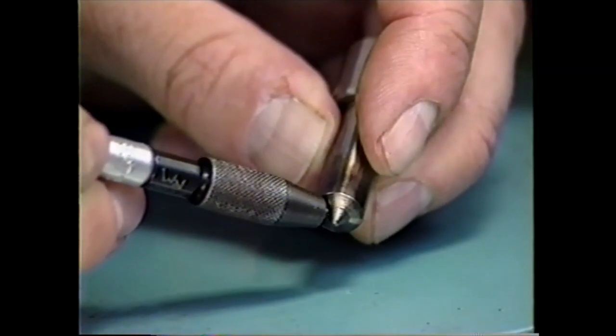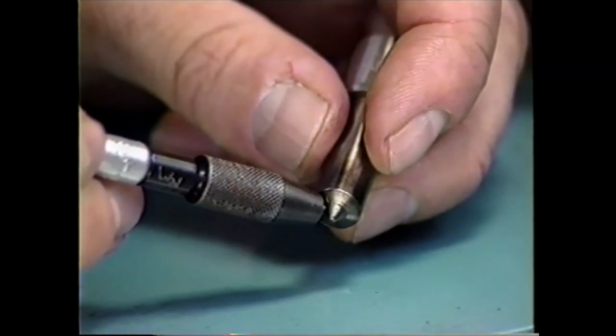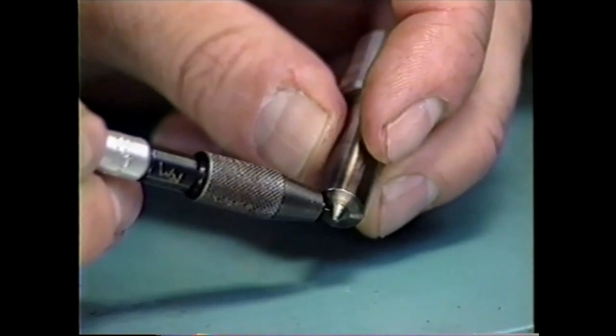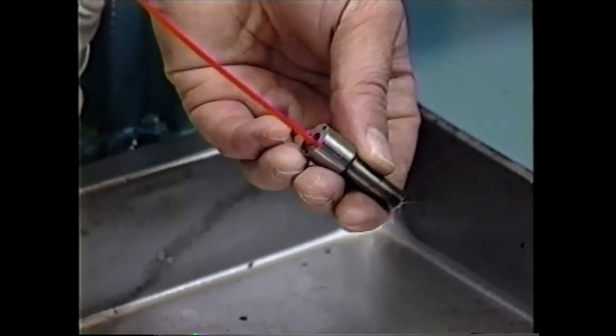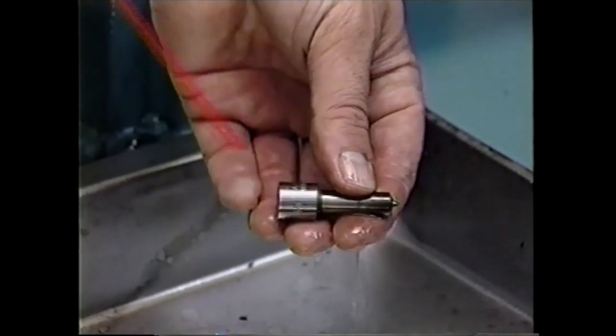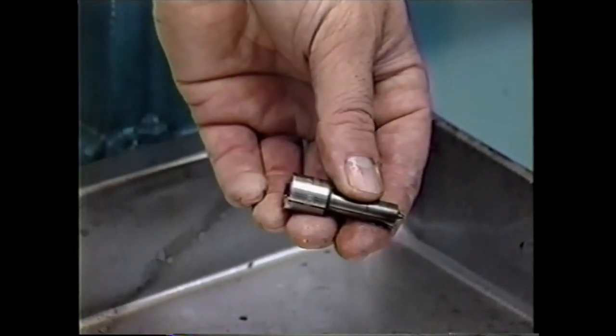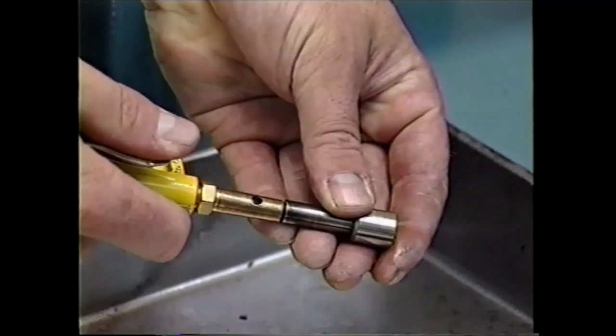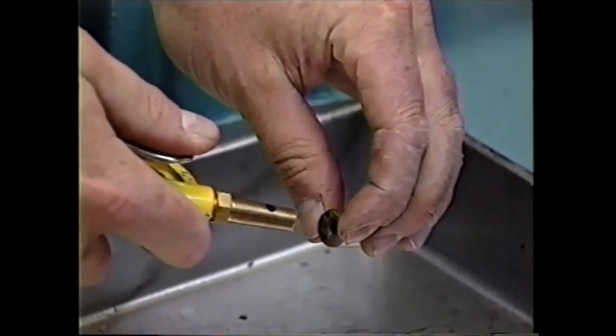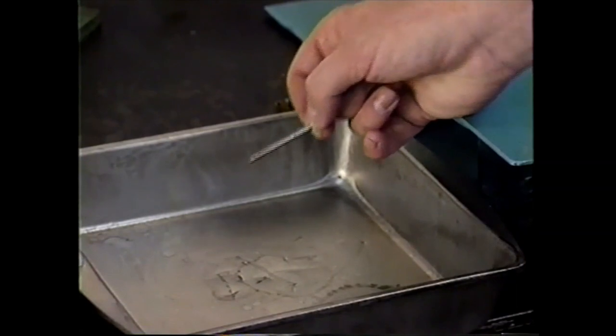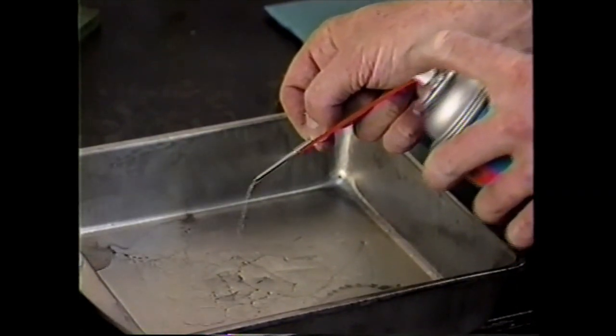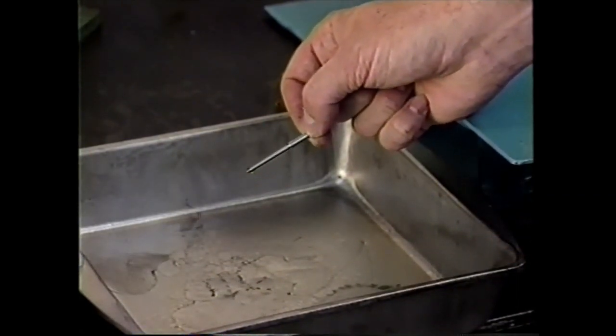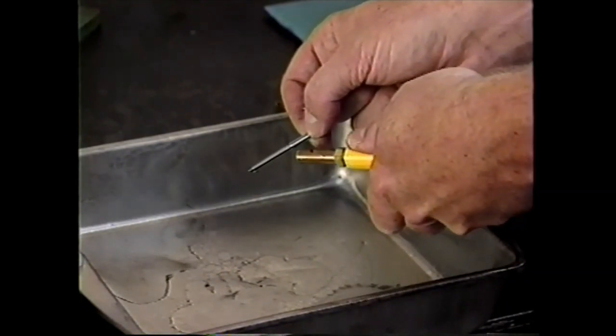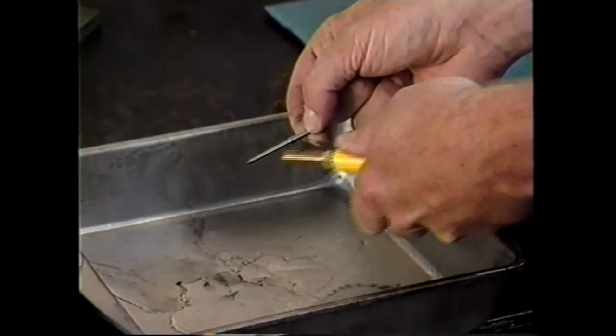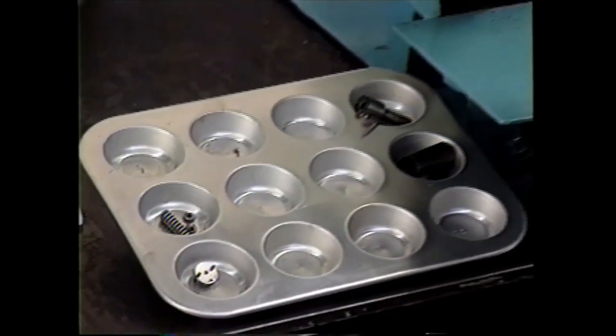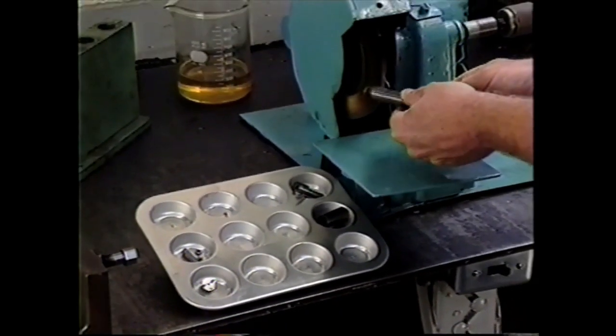Clean the spray holes in the nozzle tip with the correct cleaning needle. Remove any combustion deposits in the nozzle tip with a commercially available cleaner, and dry the part using moisture-free compressed air. Also use combustion cleaner to remove any deposits from the needle valve. Do not use a wire wheel or scraper of any kind to clean the needle valve. Clean all remaining parts with the brass brush or brass wire wheel.